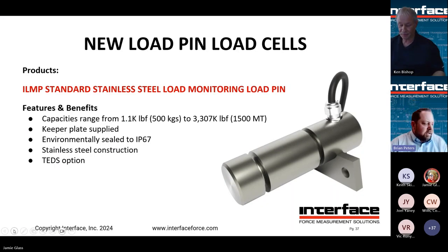Now let's move to load pins, shackles, and tension links. Our ILMP line of standard load pins is ready to go with a wide range of capacities from 500 kilograms up to 1500 metric tons. Keeper plates are supplied, standard IP67, stainless steel, and TEDS is an option. 150% safe overload, typical 300% ultimate load rating, and performance in around the 1% range. A lot of load pin performance comes down to the quality and tolerances of what the pins are fitting into, both from the load introduction standpoint and the reaction faces.